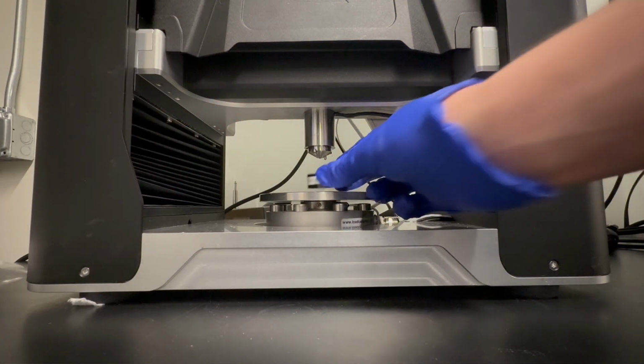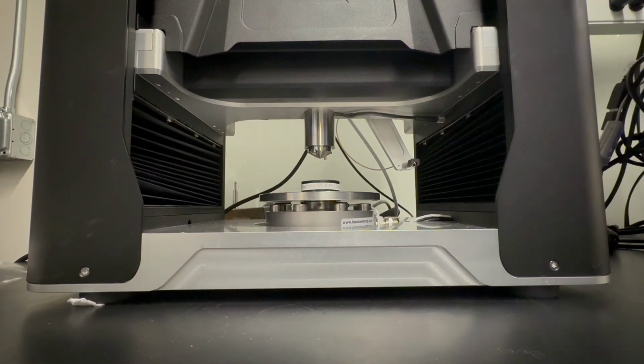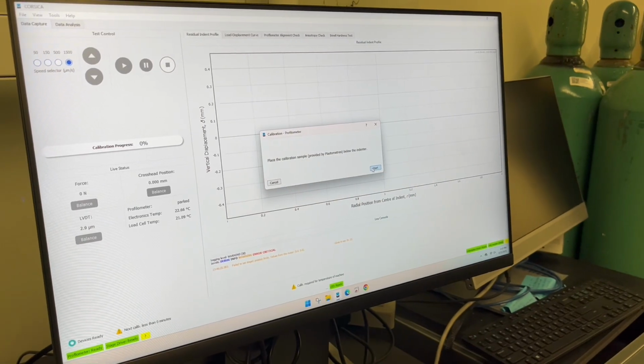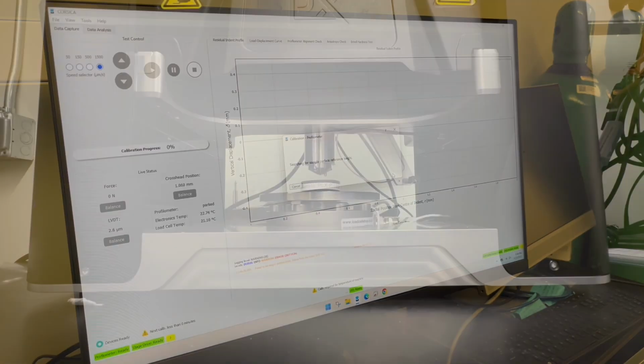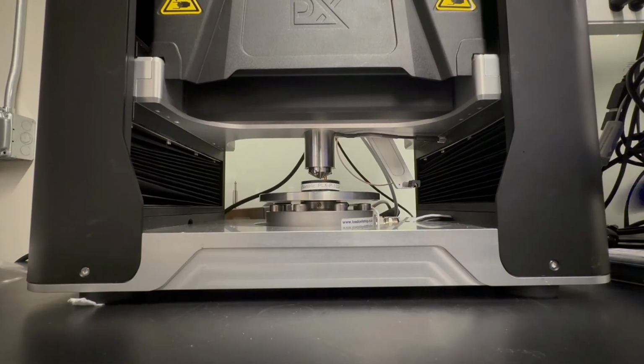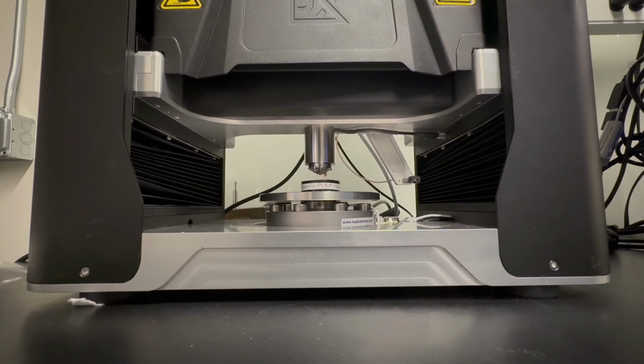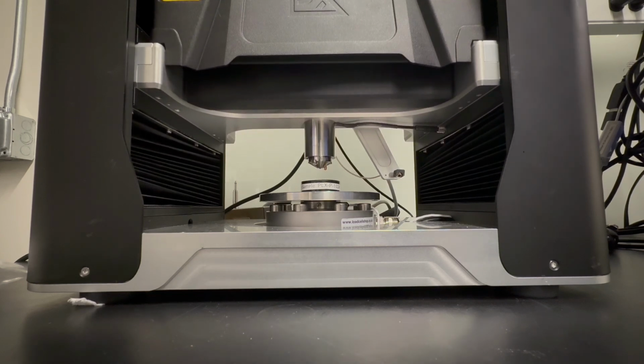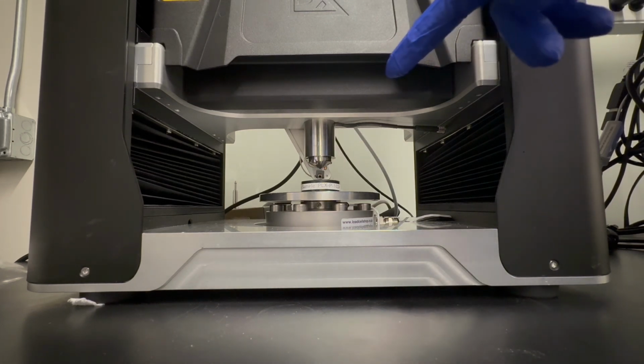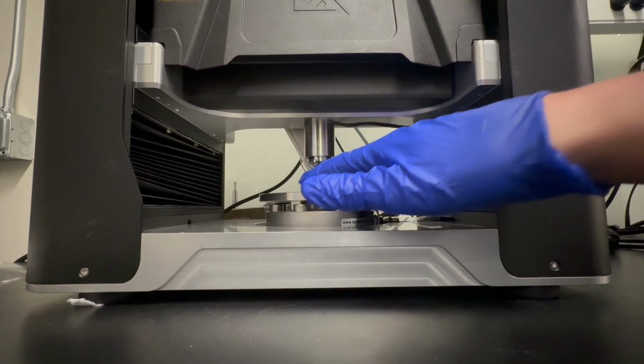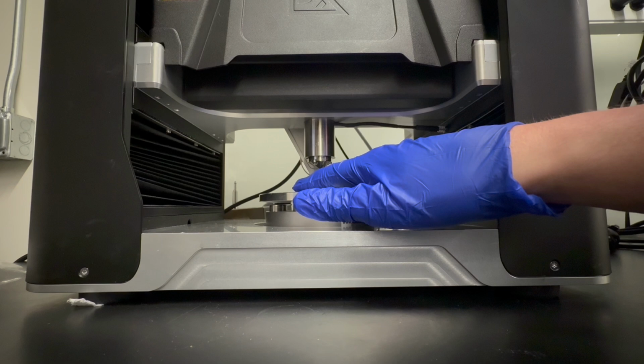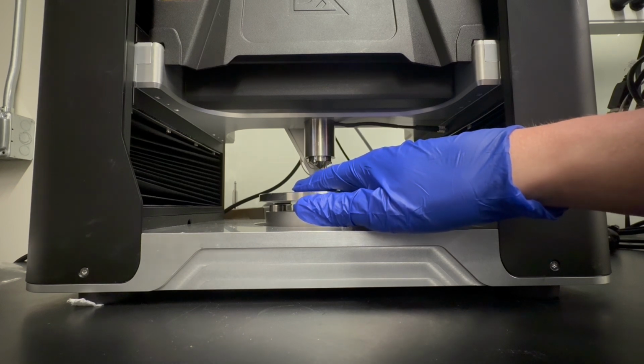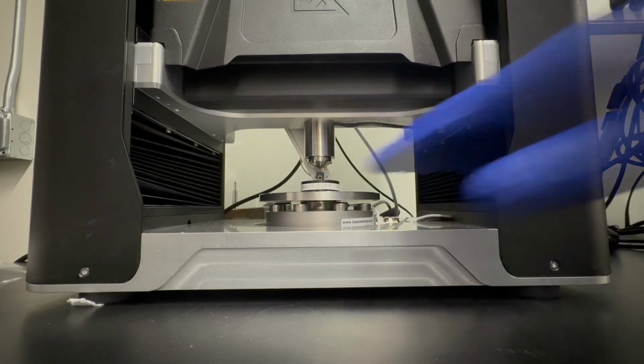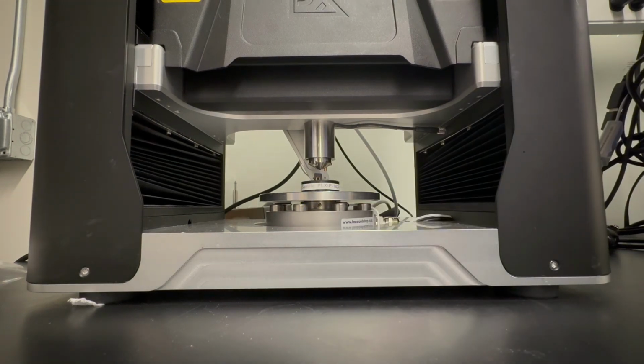Then you're going to place the calibration sample onto the plate, being very careful not to touch the profilometer. Then you're going to press start and make sure the depth matches the depth on the sample container. This is what the profilometry calibration looks like sped up, and that arm on the right side is the profilometer. Now, once the profilometer is over the sample, you're going to go ahead and adjust the sample so that the profilometer is as close to the indent as possible. Now the profilometer will calibrate for several minutes.